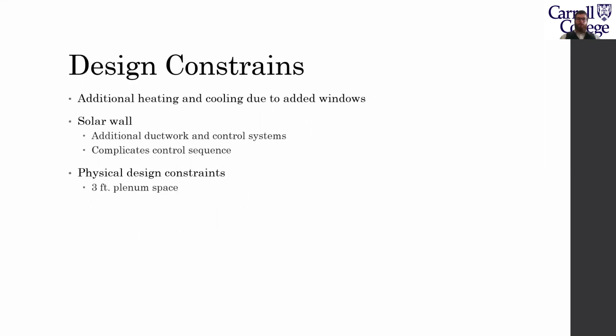Design constraints for this building include the additional heating and cooling load due to added windows, if the 12-window option is used over the 6-window option, the solar wall, which requires additional ductwork and control systems and complicates the control sequence, and the physical design constraints. There's only 3 feet of plenum space, which is a space between the top of the ceiling tiles and the bottom of the roof, which means that there's less room to run ductwork.